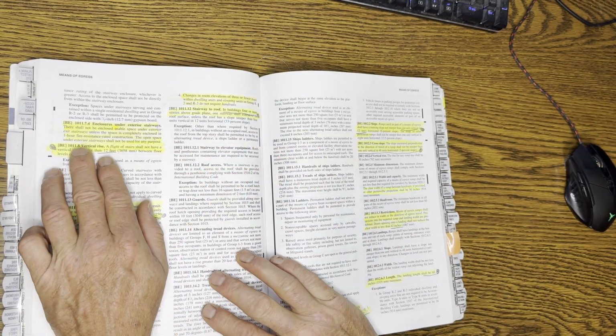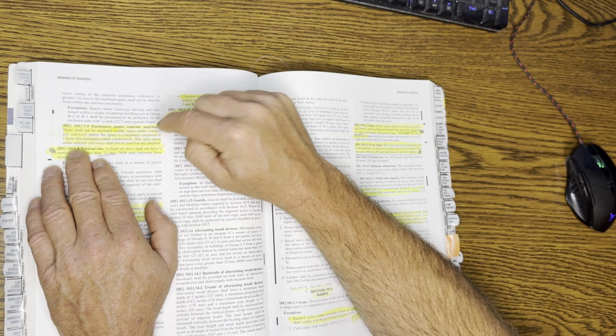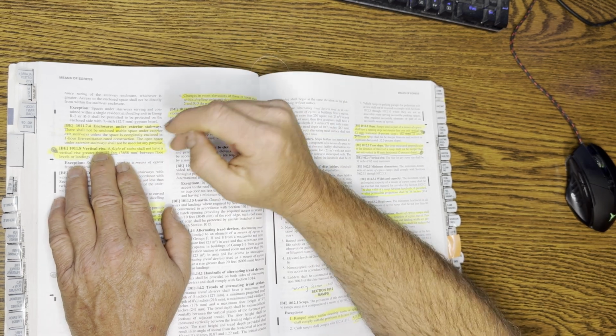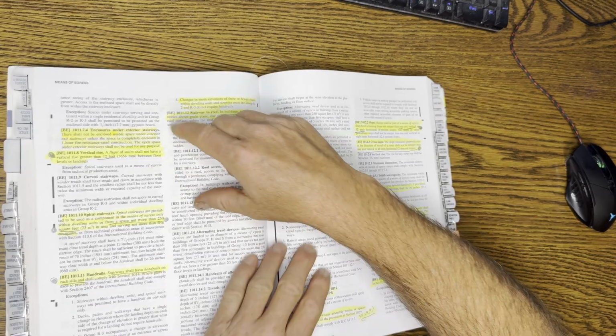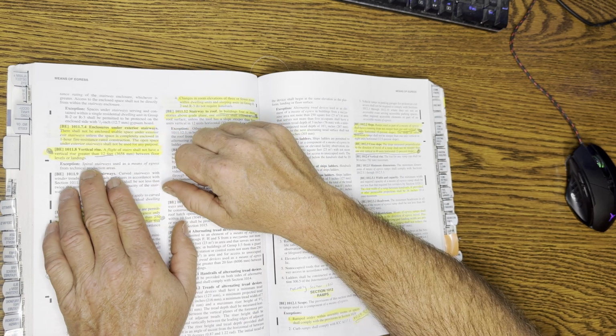Okay, keep in mind, thou shalt not have storage under exterior stairways. Period. You can't do it. In fact, you can't have it within interior exit stairway enclosures either, unless you have 1-hour fire resistance rated construction. Chapter 7 of the IBC goes into that a little bit more, but just keep that in mind. This is very, very clear. You're not allowed to. Test question.